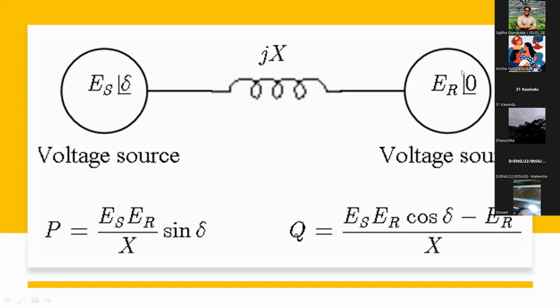In this case, as they have defined one voltage as 0, you just get delta here. If you have delta 1 and delta 2, it should be delta 1 minus delta 2. You have to understand that delta means the angle difference. Depending on the angle difference, it decides the direction of the power - whether it flows from the left side to the right side or right side to left side. The direction is defined by this delta. In other words, active power flows from the higher angle to the lower angle. Wherever you have the higher angle, active power flows from that point to the lower angle point. If this is 30 degrees and this is 15 degrees, then active power will be flowing in this direction.